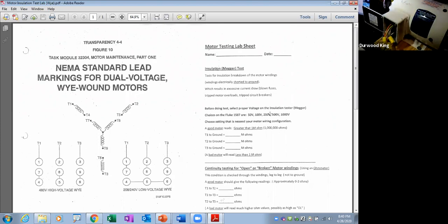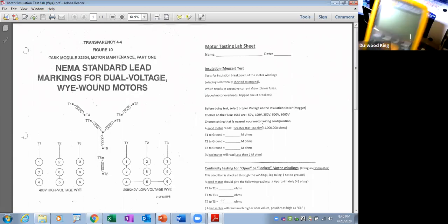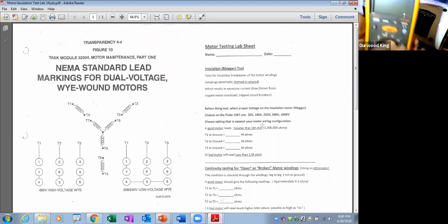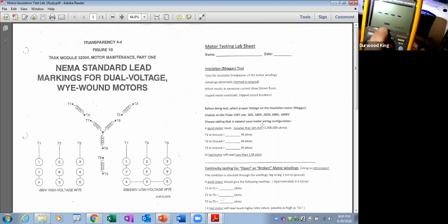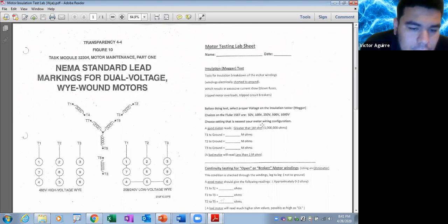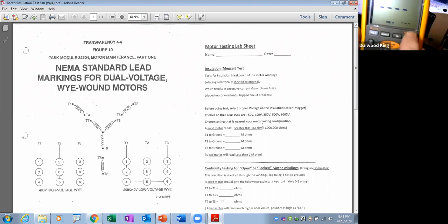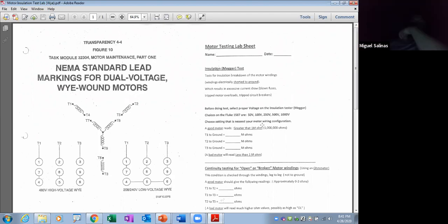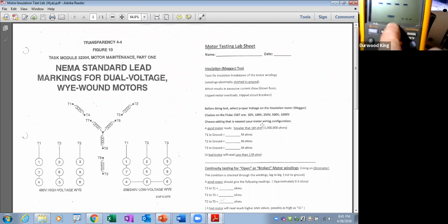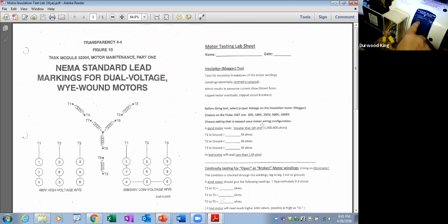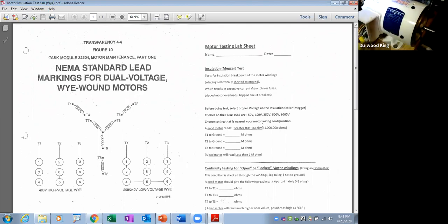So your guidelines on your testing is going to be this. If you take a look at the sheet, you select the voltage on your insulation tester that it's going to produce. It's going to be near the rating of the motor. So I'm going to show you basically here. If you look on the meter, if I flip it to insulation test, I go over to here, and if you look up here, it says what, 500? Do you see that? Yeah. Now, if I hit range, it's going to change. What does it say now? 1,000. If I hit it again, what does it say? 50. How about now? 100? 200. 250, and then 500. Yeah. So we're going to check it at 500 because it's a 460. It's a 460 rated motor, and the nearest voltage you can check it at is 500.